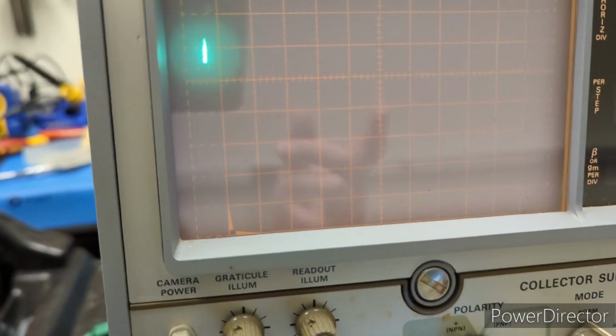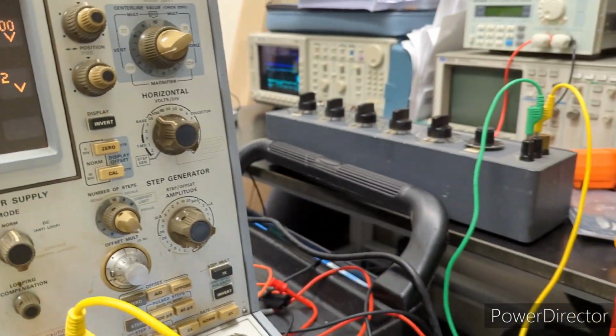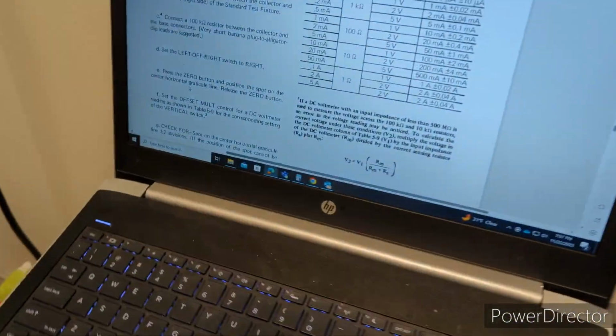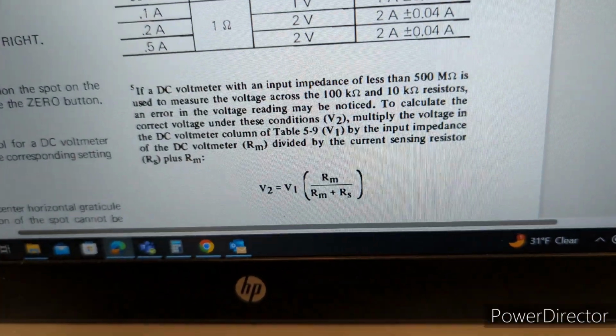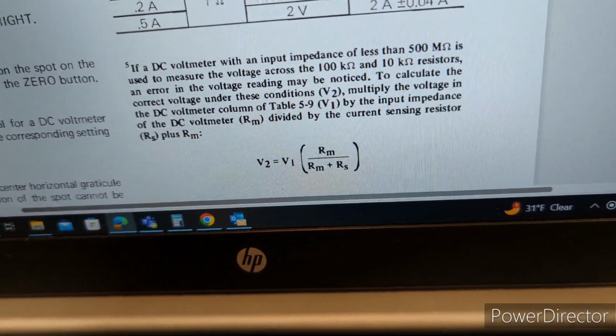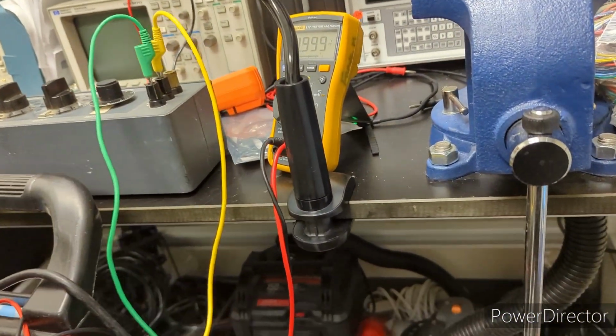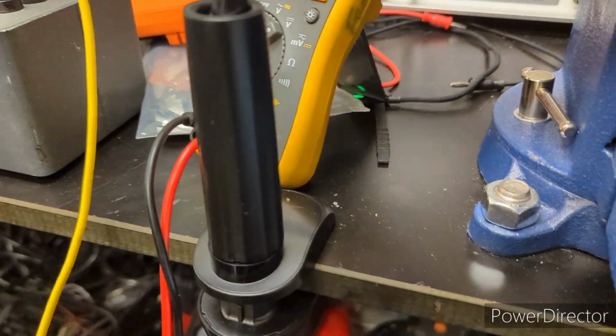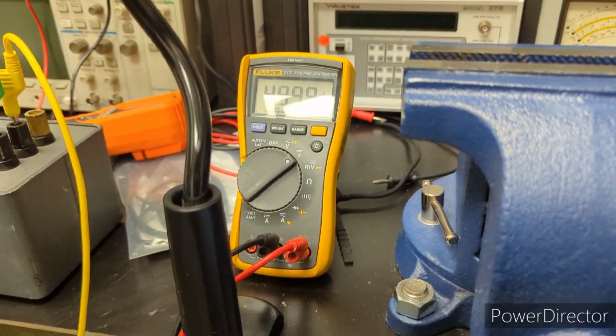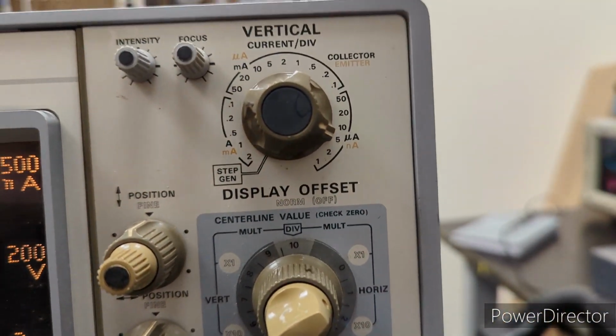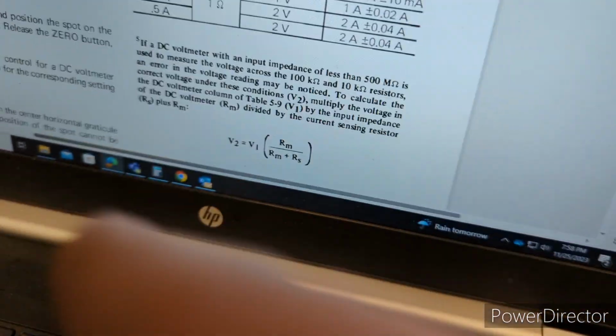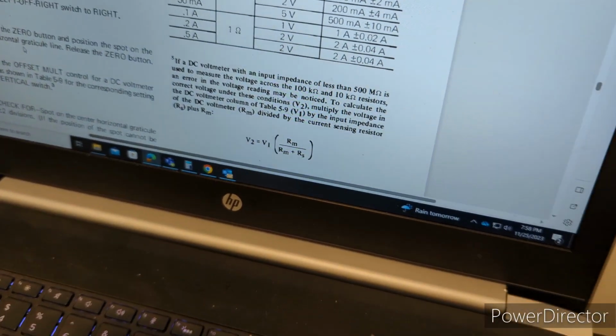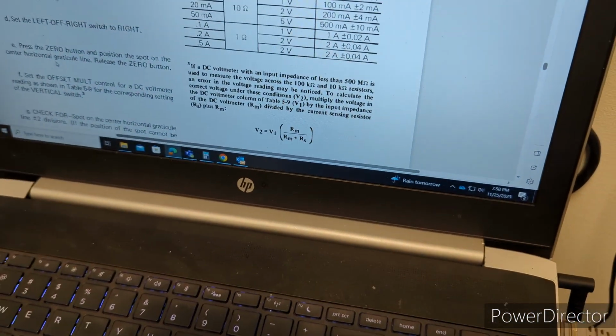At first I was thinking maybe there's an issue with the instrument, but there is a footnote in the service manual that says if you're using a DC voltmeter with input impedance of less than 500 megaohms, and this meter clearly has an input impedance less than 500 megaohms. I think it's 10 megaohms, like a lot of meters are. So that could explain the difference that we're seeing. So we have 5 volts, it should be centered for the 5 microamp setting of the switch. They do give a formula that you can use to calculate that error, and I guess I can give that a try. I'm a little bit curious to see, so why don't I do that, and let's see what we get.